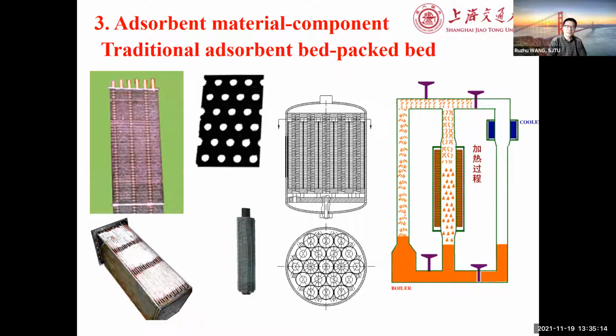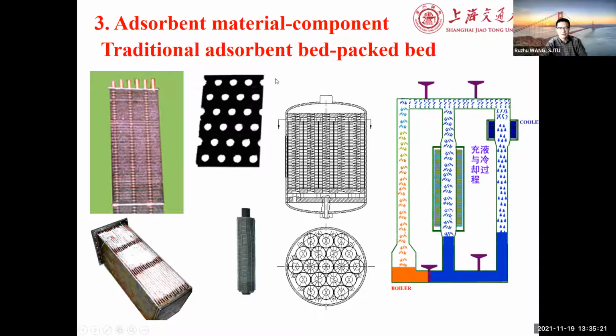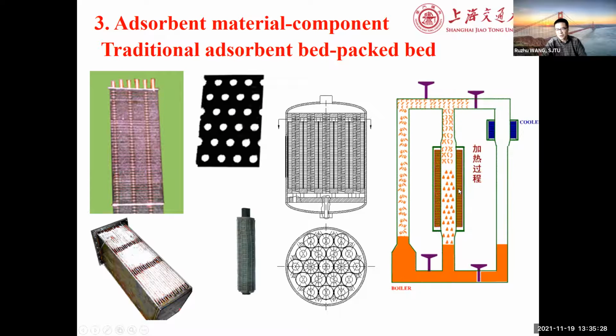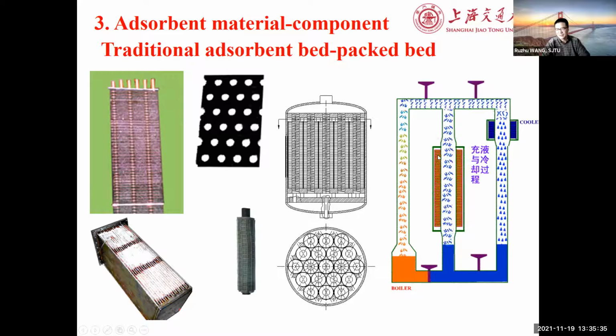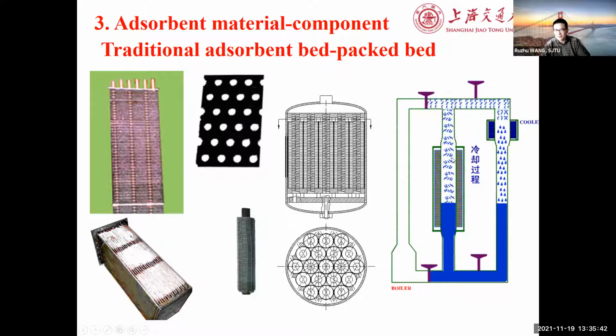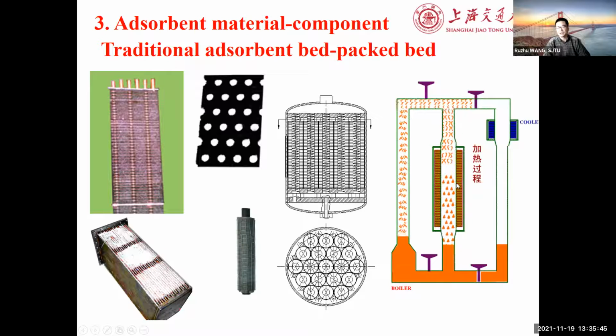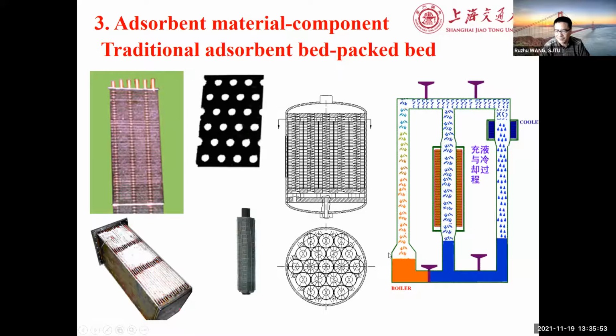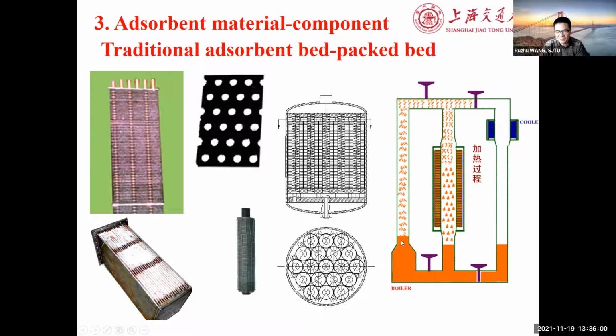So after this kind of material research, we need to work on the component and the equipment. In this case, you need to design an adsorbent bed, possibly a packed bed, integrated with heat exchangers, and you consider how to provide heating of the adsorbent and also how to cool down the adsorbent. When it's heated, you get regeneration, the desorption of refrigerant. When it's cooling down, then you have the refrigeration, evaporation, and adsorption process. This just shows if you have a thermal siphon and use a boiler here for heating and a cooler here for cooling, then you could very easily operate, and no pumping is needed. So this was our design for the adsorption system.